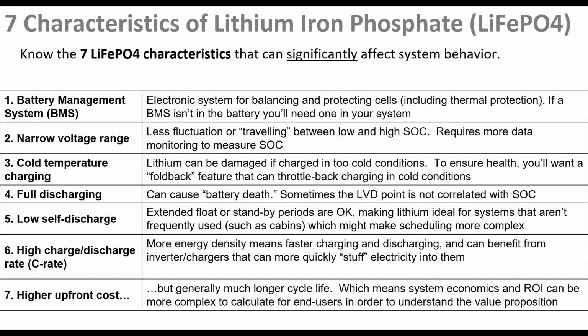You've got extremely low self-discharge with lithium batteries, so extended periods of time are okay, but you want to be sure that systems that aren't frequently used will be okay during that extended period of float. That's something we also put into the charging stages of the battery, because with lead acid you'll see a much higher discharge rate if it's just standing and not being used. With lithium, I think Bob had said 1% per month, which is really minimal.